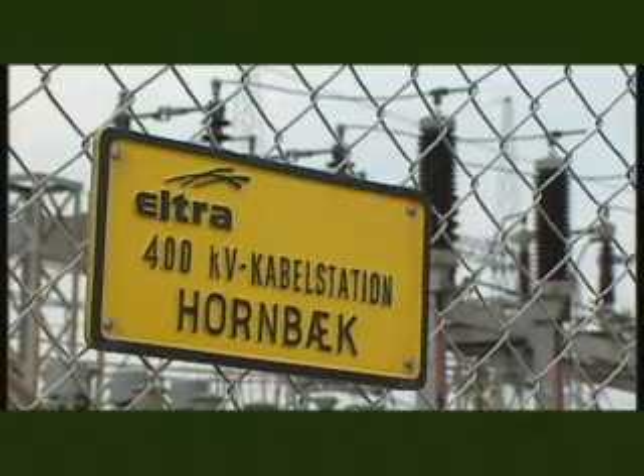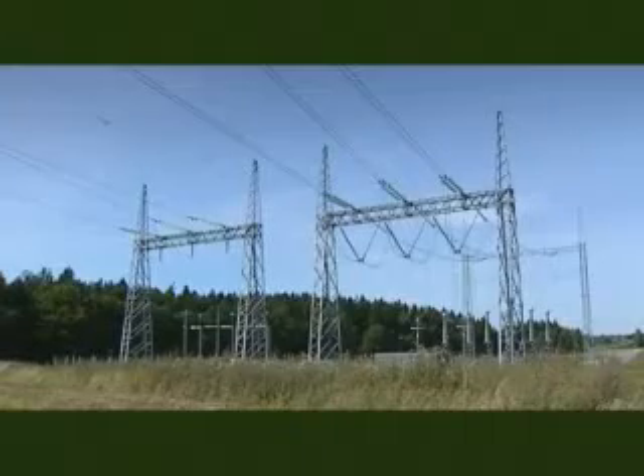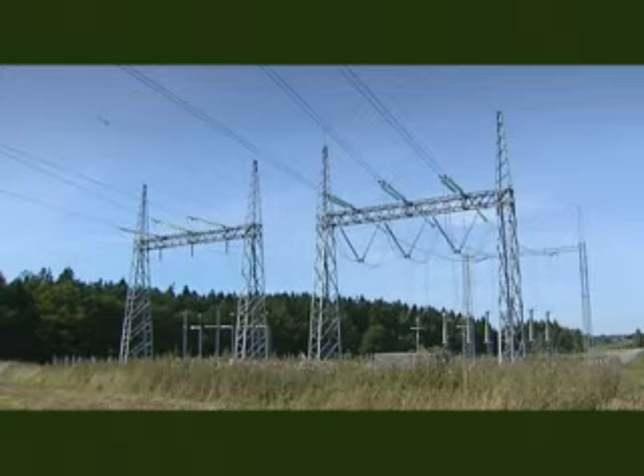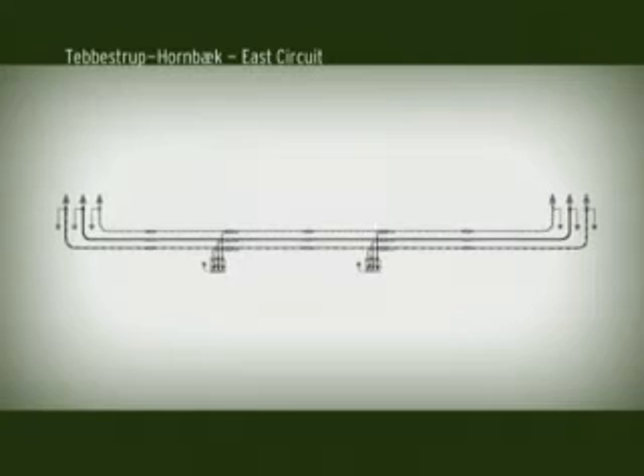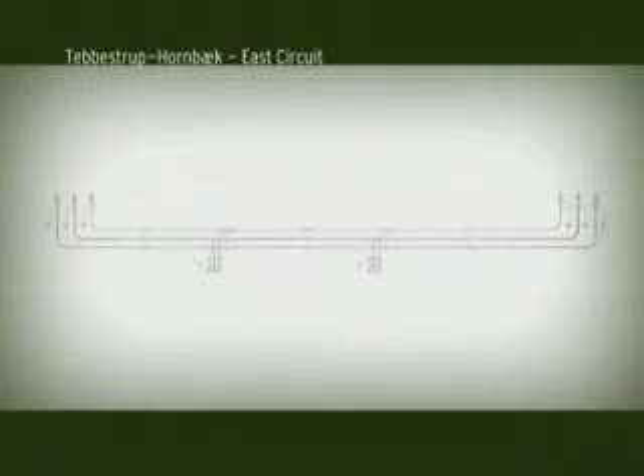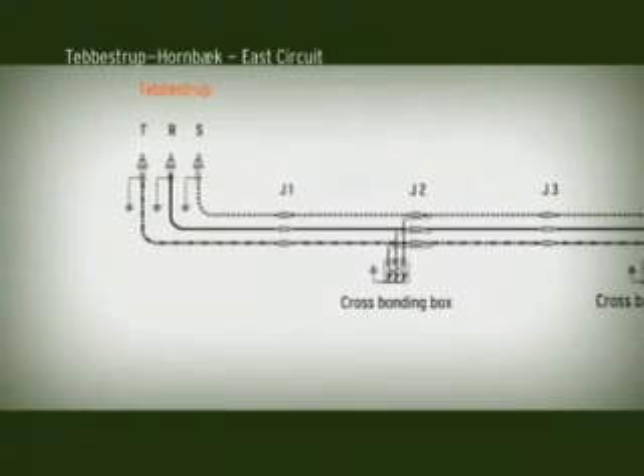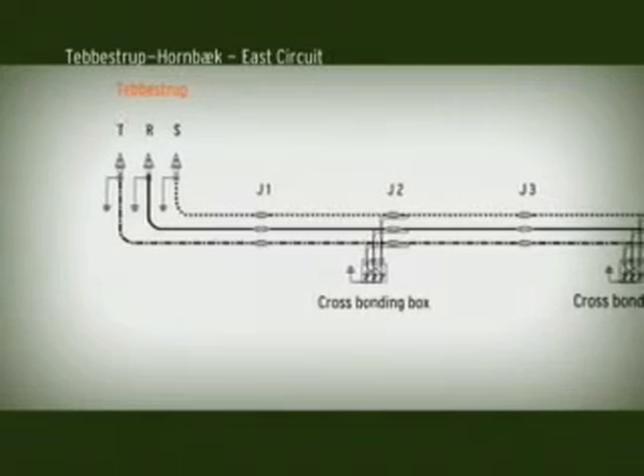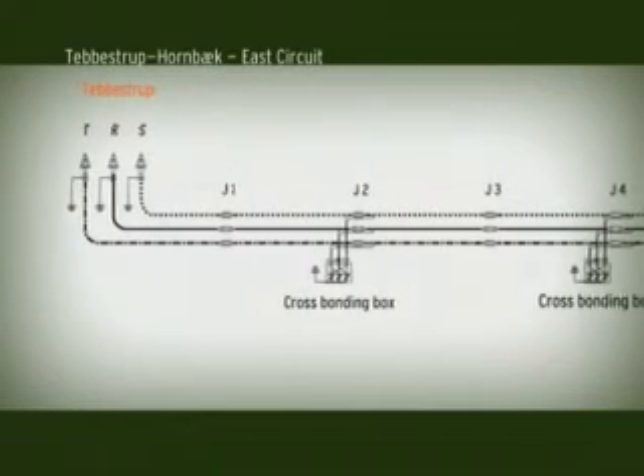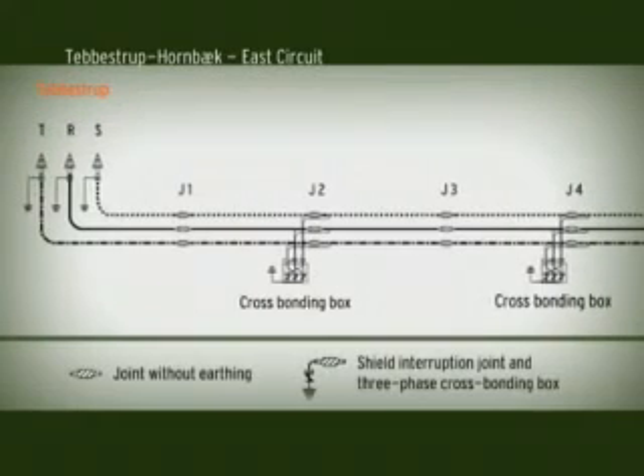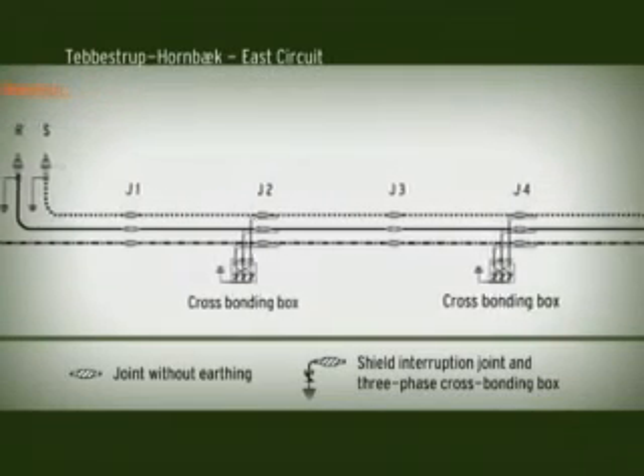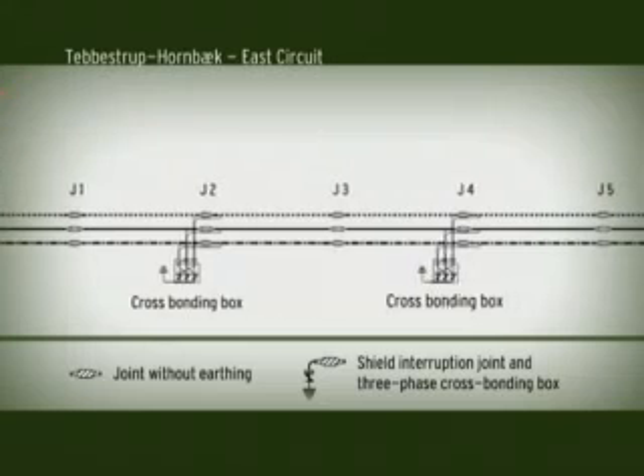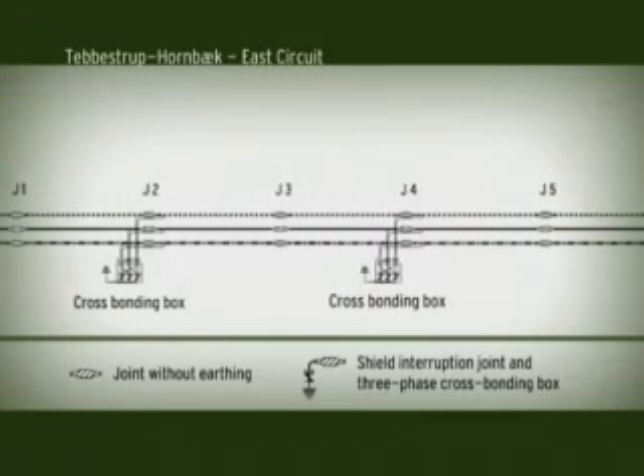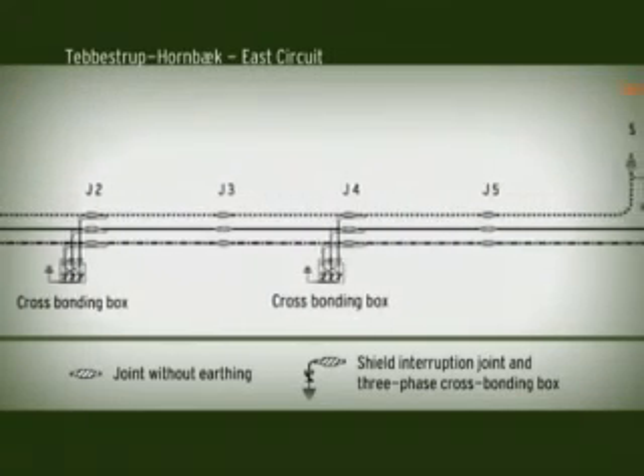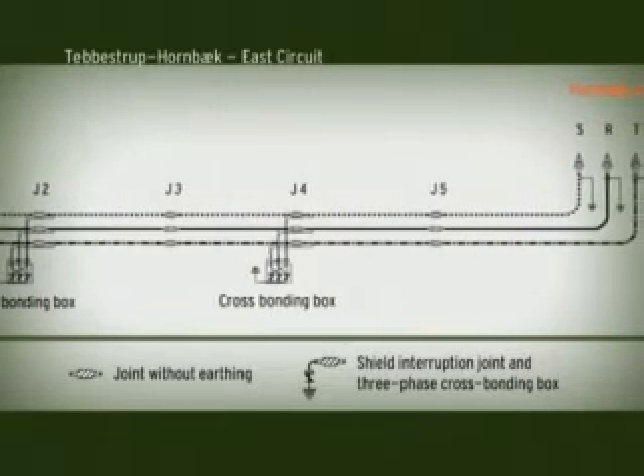At compound Hornbæk, which lies approximately 2 kilometres north of Gudenå at Randers, the 400 kV line continues as an overhead line to the cable transition compound Catbia. There are 5 400 kV joints on the Gudenådalen section. The shields of the 400 kV cables are cross-bonded to achieve maximum transmission capacity. There is no phase transposition. The 4.5 kilometres are divided into 3 parts, each 1500 metres long. Each part consists of 2 cables which are joined without shield interruption.